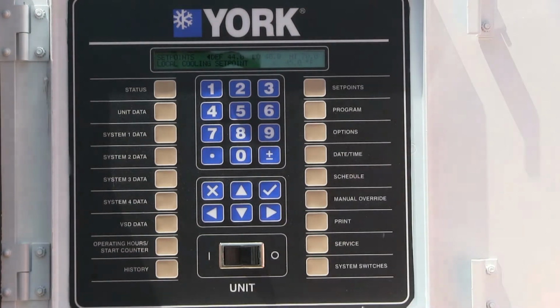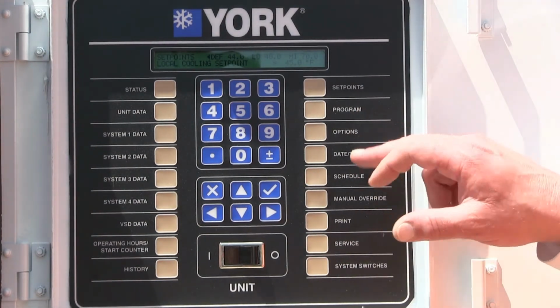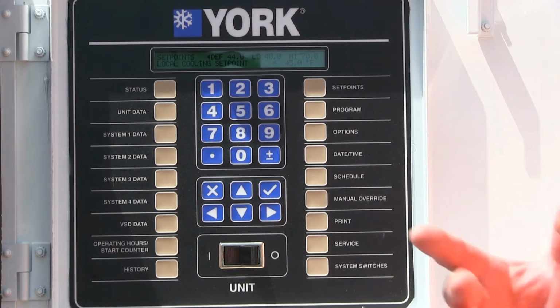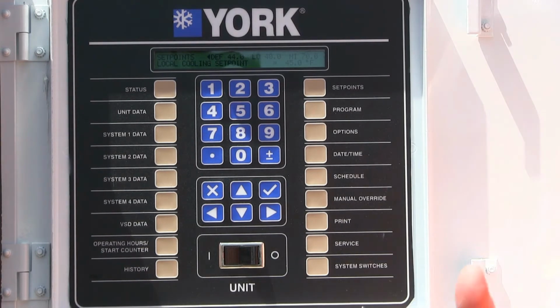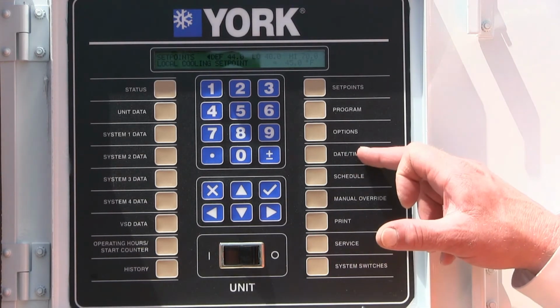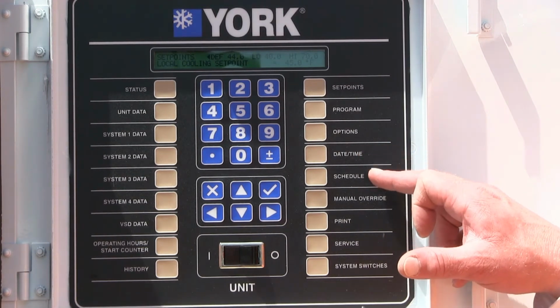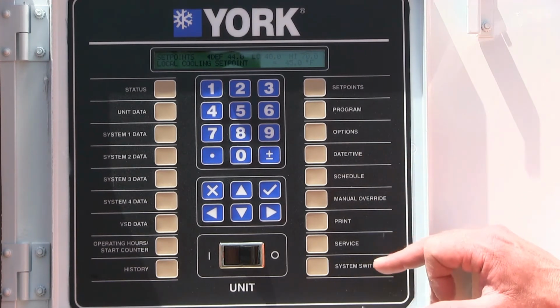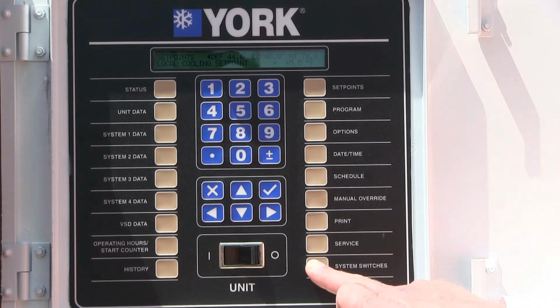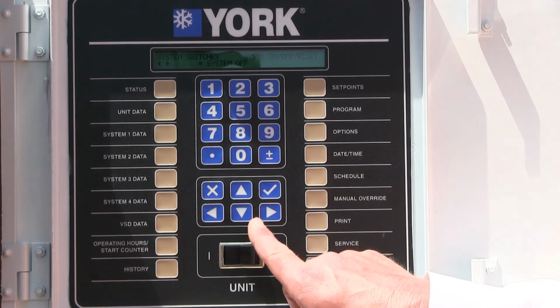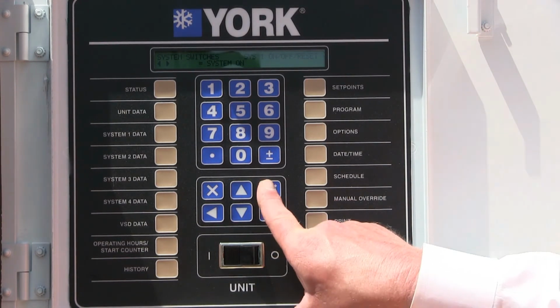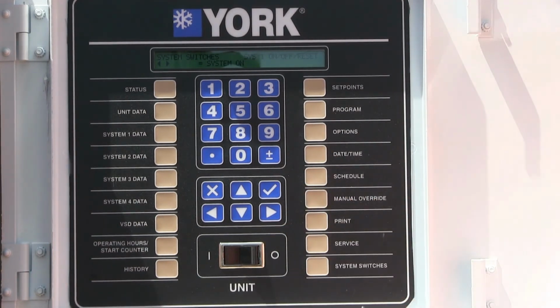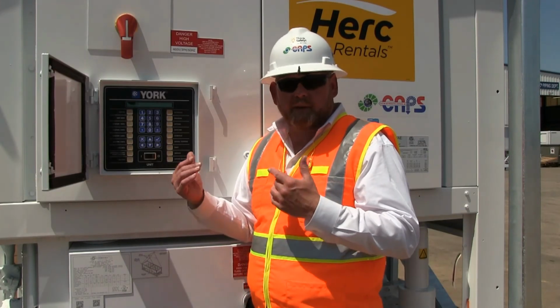We push the enter button there. Our programming options, from time to time you'll have a few items that have to be changed in there, such as low ambient cutout or low leaving liquid fluid cutout. And then the date and time, we talked about the time of the day, schedule, manual override, and then again the system switches, very important to start the machine. You're going to come back here, turn that back to on, push the check mark, and that'll start the chiller back up and going. As you can see, very simple to operate, very easy to use.